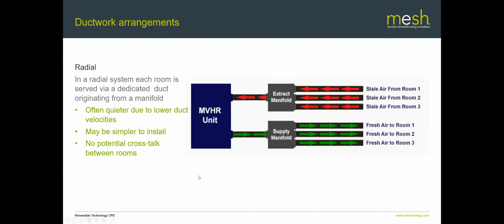So what's the advantage of that? Well, sometimes they can be a bit quieter because you can reduce the duct velocity in each one of those little branches, because the air is only serving one particular room. It might be a simpler install because you're tending to use semi-rigid ductwork rather than rigid ductwork for these branches. Each of these spokes of the radial wheel is a small duct, and it's semi-rigid, so it's one continuous piece that looks like a giant Hoover tube. We'll talk about that a bit later on. So it can be a bit simpler to install.